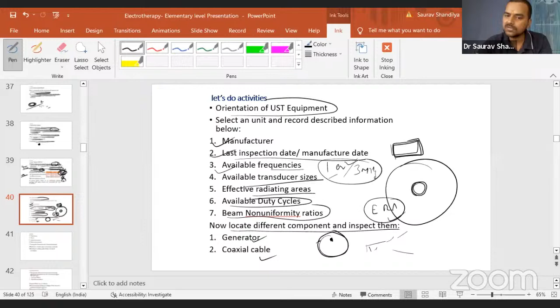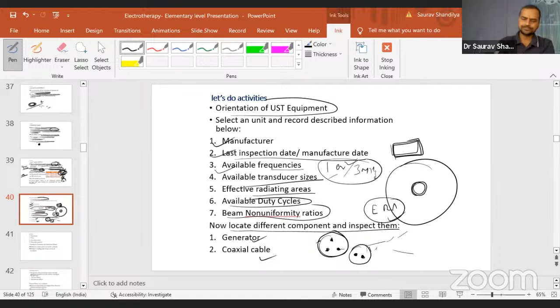Now don't ask me whether it's a 2-wire cable. You will see in an ultrasound, there is a 3 wire. Okay, there is a 3 wire. You must have seen it, many of you. And there are few cables, I have not seen much, that is with the 2 wires also. It is okay to have 2 or 3, there is no problem, but you should check that properly whether that is fitting or not. Then you should always check the transducer, because I always believe that in ultrasound the most important part is the head transducer.